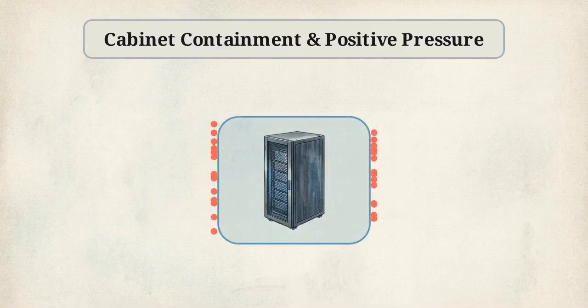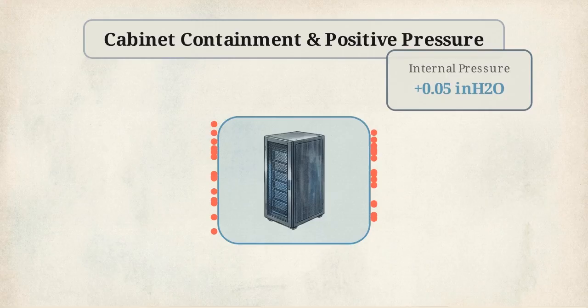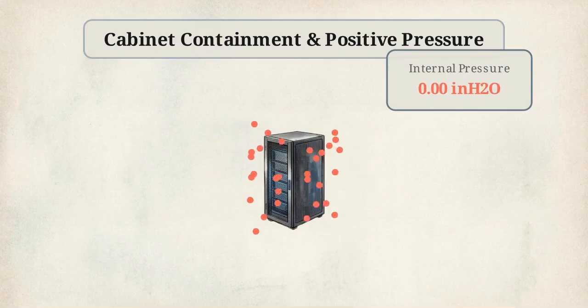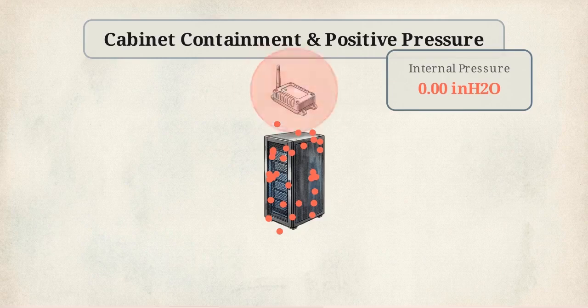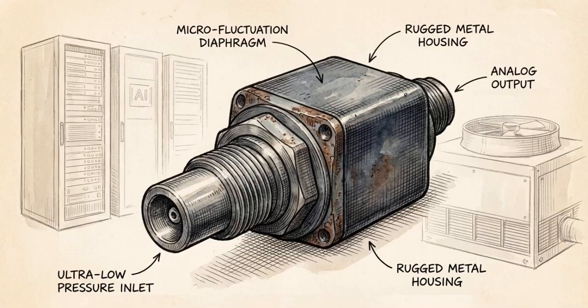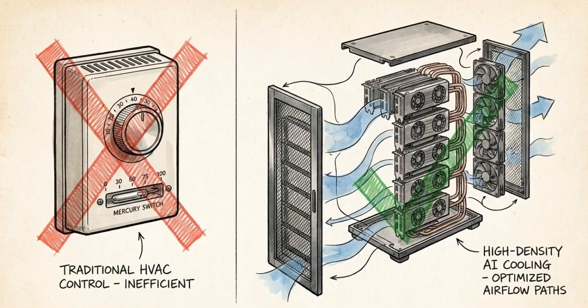Inside the server cabinets themselves, facilities maintain a slight positive pressure. This ensures that conditioned air flows strictly outward, creating a thermal barrier that prevents external contaminants and hot exhaust from leaking back in. A sudden drop in that pressure profile instantly flags a containment breach. A technician leaves an aisle door open or a ventilation fan degrades, and the thermal delivery is compromised. Capturing these micro fluctuations requires ultra-low-range air pressure sensors, deployed exactly where the air enters and exits the controlled zones. By tracking pressure differentials instead of relying solely on thermostats, operators prove that the required volume of cooling is reaching the hardware before the equipment heats up.